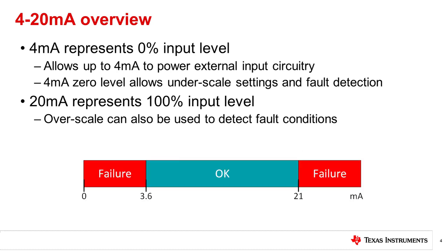A 4 milliamp zero level and 20 milliamp full scale level allow for fault detection in the system. Zero amps on the transmitter output would indicate that there is a break in the transmission line. Smart measurement devices can also detect internal faults such as sensor failure. The NAMUR NE43 signal standard allows for the user to set an underscale or overscale failure mode that will output a 3.6 milliamp or 21 milliamp signal for at least 4 seconds to report a failure to the control station. 3.6 milliamps, 21 milliamps, and 4 seconds are used to avoid false alarms. The 4 milliamp zero level also allows the transmitter to supply up to 4 milliamps of current to power external input circuitry. We will introduce that capability in a future video.